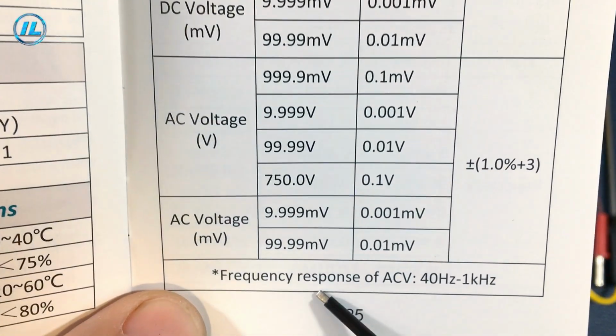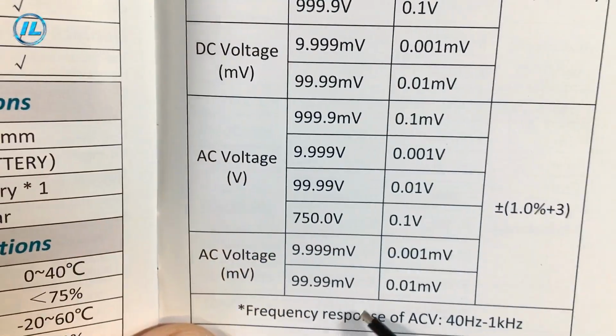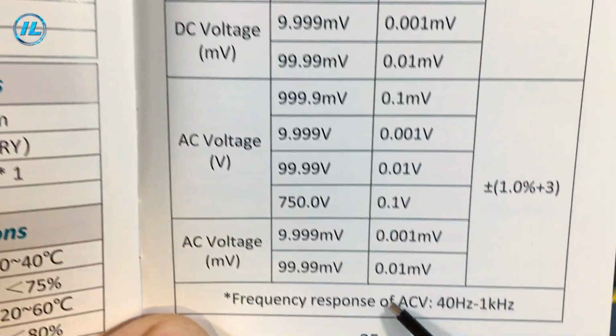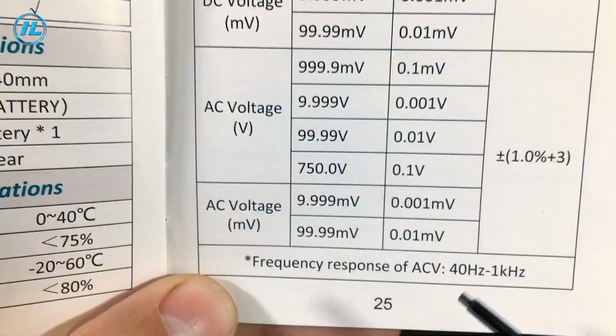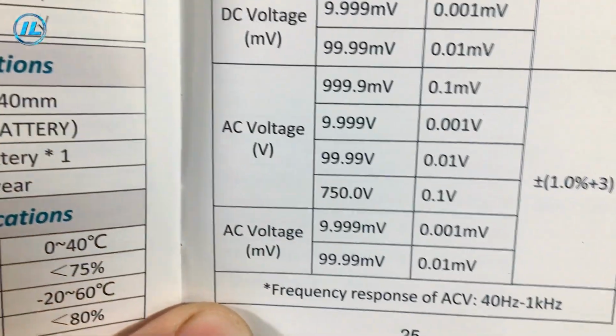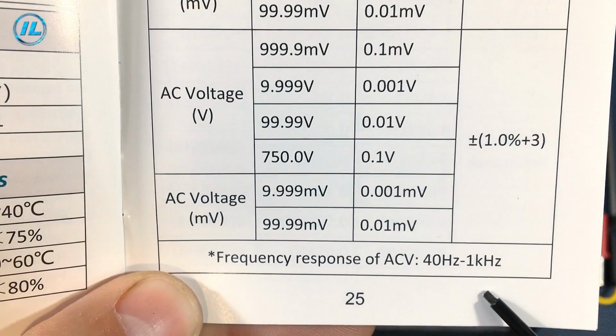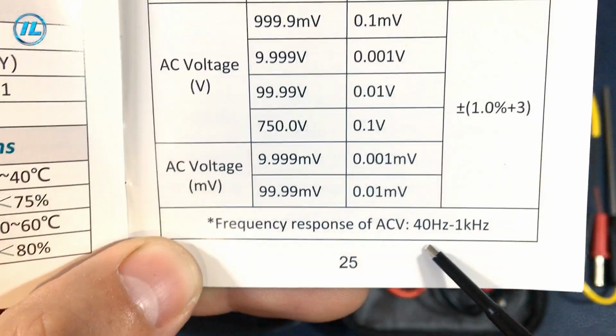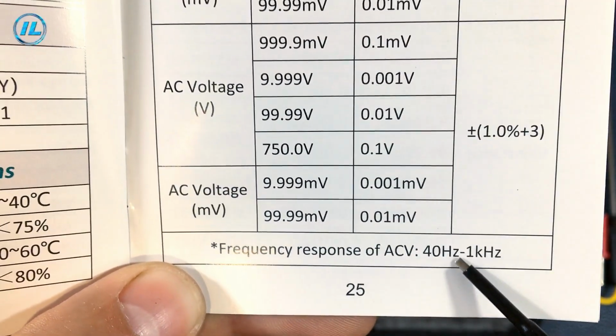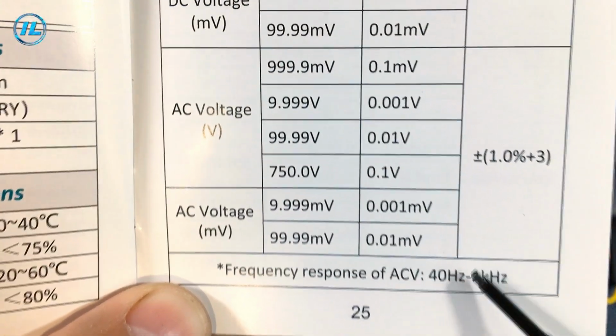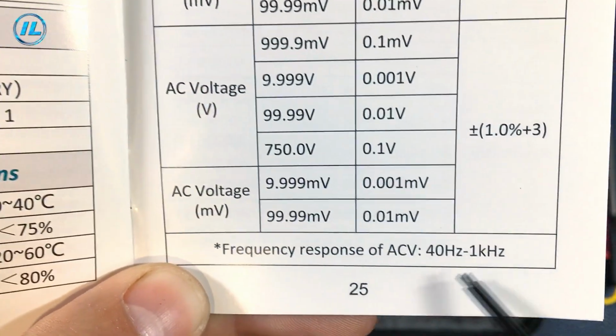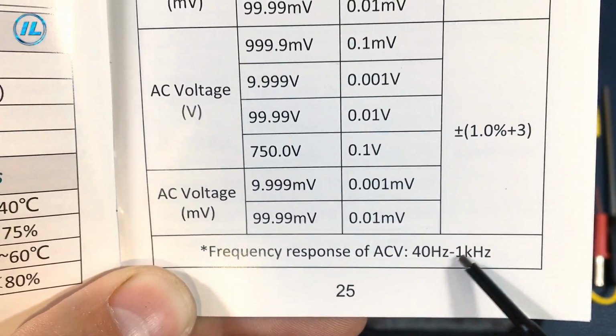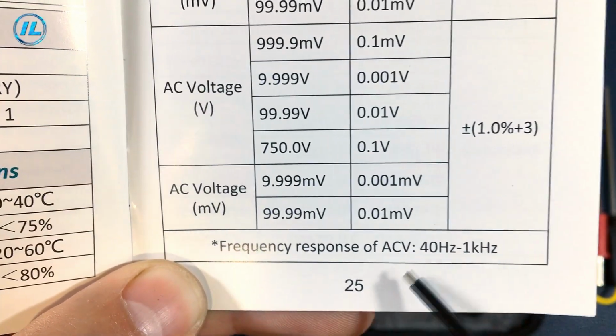The following is very important information. This multimeter has a true RMS function. That is, it can measure voltage and current regardless of the waveform and at high frequencies. But it is honestly stated here that the frequency range in which this multimeter makes accurate and adequate measurements is from 40 Hz to 1 kHz. Beyond these limits, measurements can be with a large error.